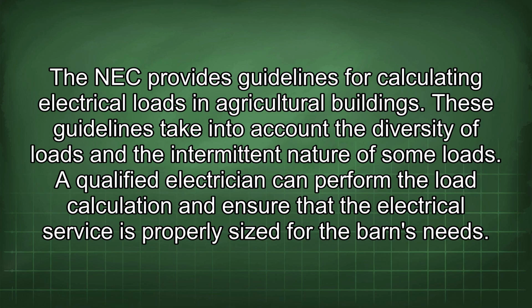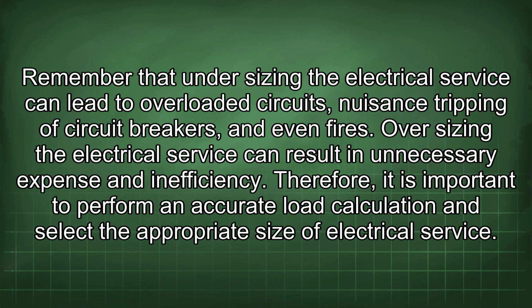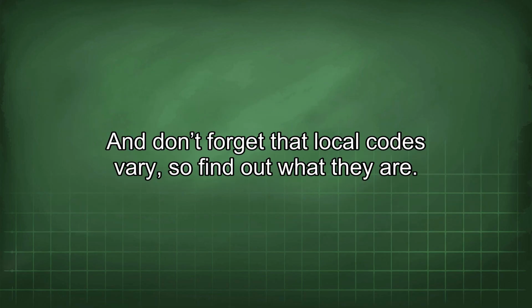A qualified electrician can perform the load calculation and ensure that the electrical service is properly sized for the barn's needs. Remember that undersizing the electrical service can lead to overloaded circuits, nuisance tripping of circuit breakers, and even fires. Oversizing the electrical service can result in unnecessary expense and inefficiency. Therefore, it is important to perform an accurate load calculation and select the appropriate size of electrical service. And don't forget that local codes vary, so find out what they are.